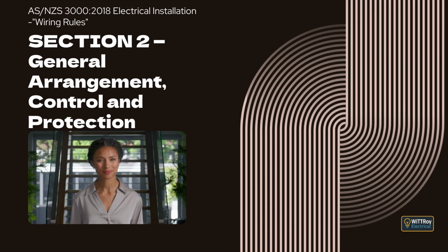The first way is automatic disconnection of supply, which is the most common method. The second way is using Class II equipment or equivalent insulation, which provides extra insulation so no exposed metal becomes live. The third way is electrical separation, where one circuit is fully separated from others so a fault cannot produce a dangerous voltage. The standard then explains that the detailed rules for automatic disconnection of supply are found in later clauses.